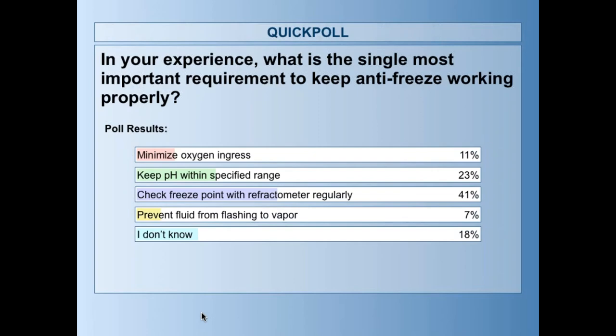For glycol, you want to make sure it doesn't end up exposed to too much oxygen, because glycol with dissolved oxygen will tend to become acidic. Each of the glycol manufacturers will state a range above which they want that glycol to stay. Otherwise, if it gets below that, your glycol is starting to become acidic and losing its properties. So that's good, absolutely.